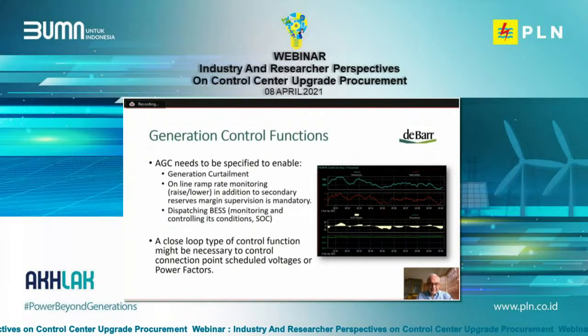Ramp monitoring is mandatory. In the past, it was enough to monitor the high and low secondary reserve. Now it's mandatory to monitor the ramp, to assure that when changes are happening in the generation, you can respond quickly without deterioration of the AGC response.